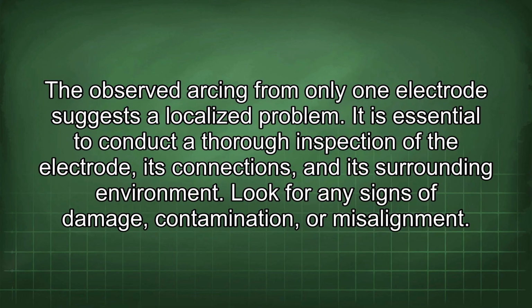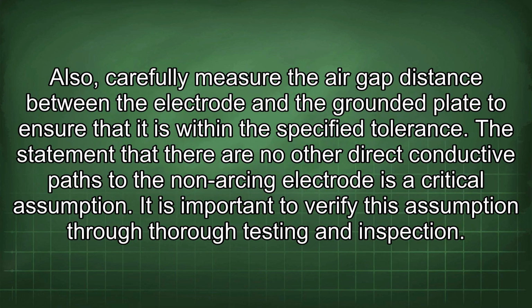The observed arcing from only one electrode suggests a localized problem. It is essential to conduct a thorough inspection of the electrode, its connections, and its surrounding environment. Look for any signs of damage, contamination, or misalignment. Also, carefully measure the air gap distance between the electrode and the grounded plate to ensure that it is within the specified tolerance.